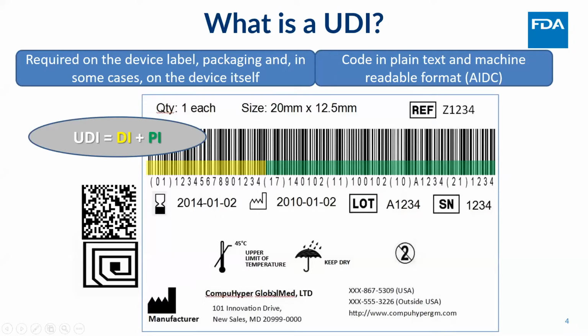As you can see on this fictitious label on the screen, this can be a manufacturer, this can be a third-party labeler. It essentially identifies those three key pieces. And that's where the potential and the power of UDI lies in several areas, such as aggregating adverse events, identifying the performance of a device specific to a given version or a model, an ability to actually identify where things changed and what happened with that change.